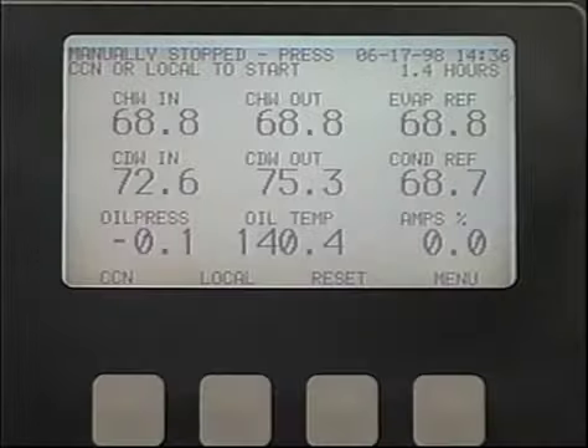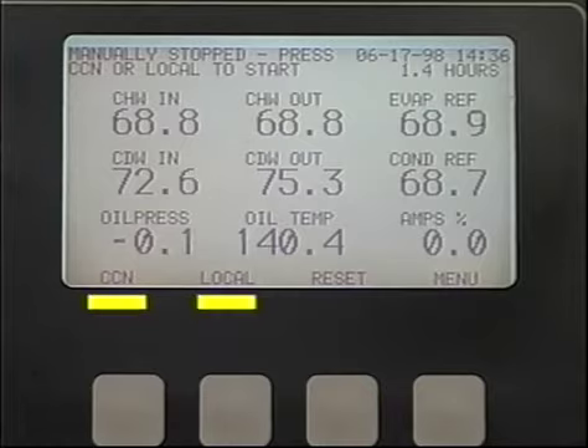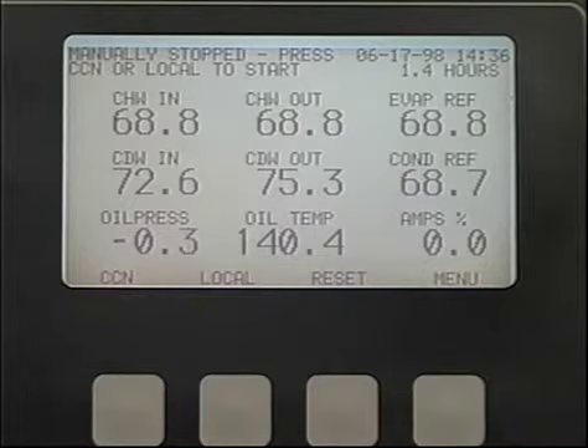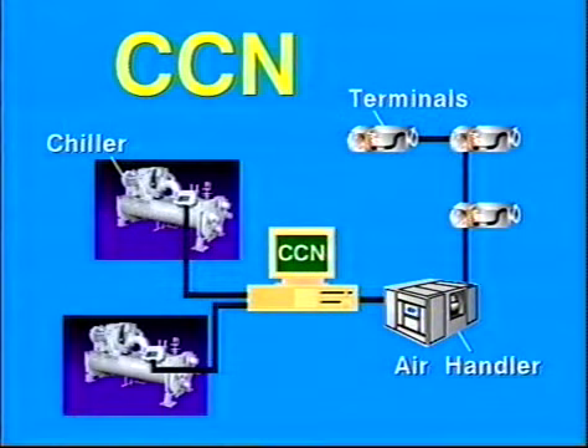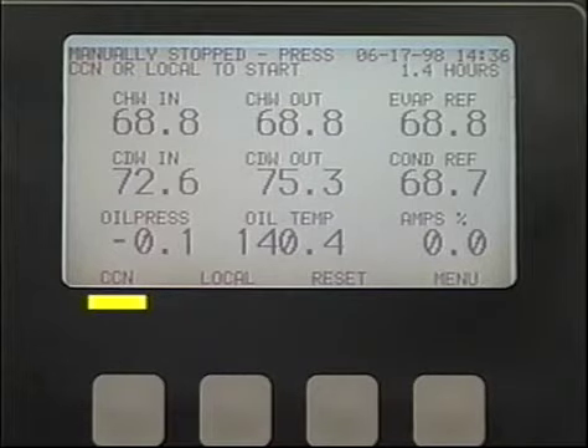Now it's time to look at the startup and shutdown sequences for your chiller. There are two modes of control, local and CCN, and a start key is assigned to each mode when the default screen is displayed. Local control is just what it sounds like. Total control of the chiller is at the local site. CCN control exists when the local chiller controls are connected to a Carrier Comfort Network system or building supervisor, where control of the local chiller may be at a remote location. Using the CCN key allows the chiller to respond to network commands.